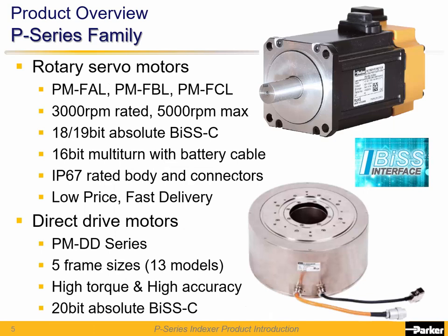The P-Series motors are available in 40, 60, and 80 mm frame sizes with high resolution BiSS-C absolute encoders. The 40 mm PMFAL has 18-bit resolution and the 60 and 80 mm sizes have 19-bit resolution per revolution, giving high stability for fast response. A battery cable provides multi-turn capability for 65,536 multi-turns.